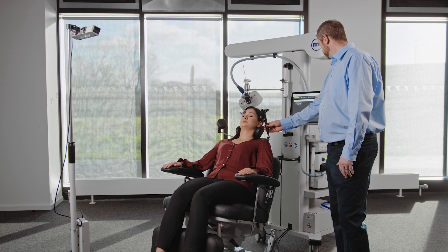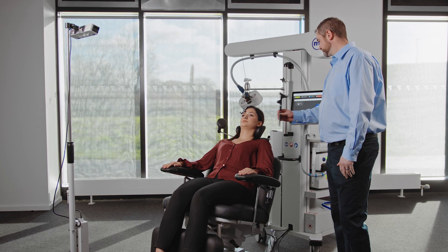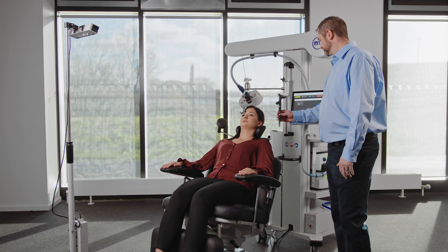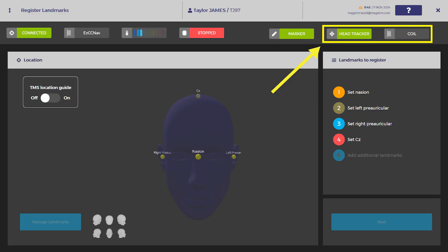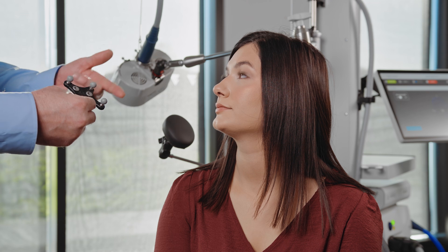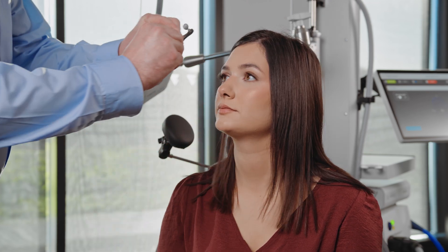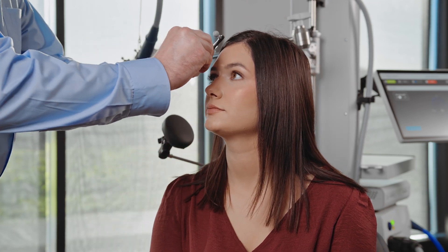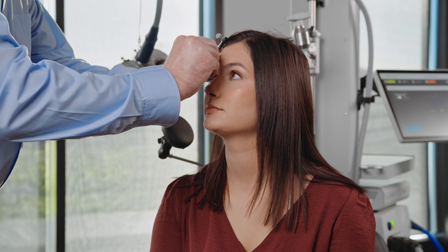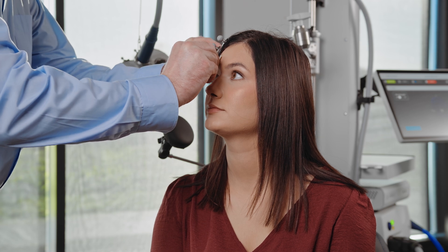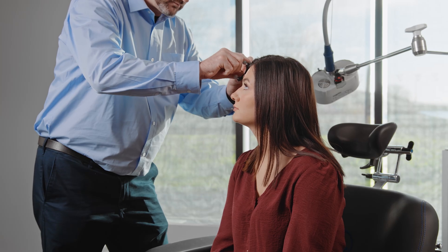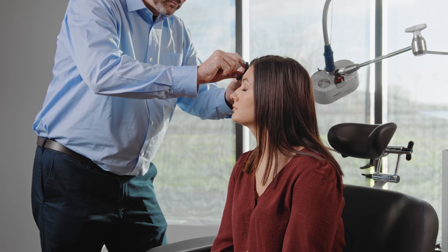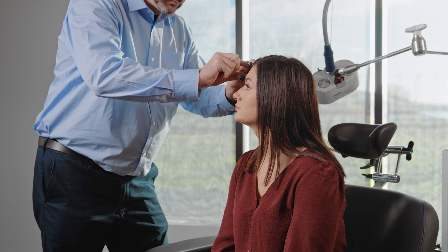Move the remote pointer tool around the patient's head to confirm the camera's field of view as indicated by turning green on the Horizon user interface. Place the head reference tool on the patient's head in a location that will be visible to the camera but not impede the position of the coils. Avoid areas like the jaw, which may be susceptible to movement.